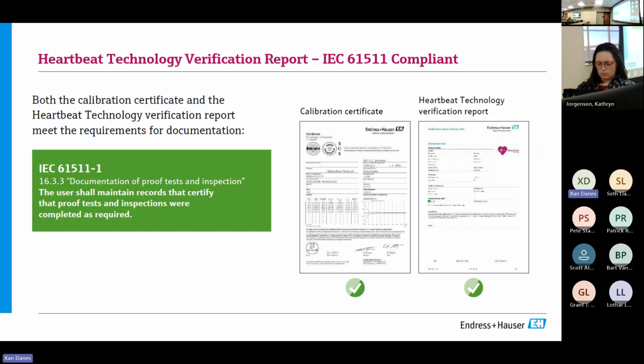So when it comes to the safety instrumented system lifecycle, the calibration certificate, and in some cases even the verification report, meet the requirements for lifecycle documentation. So being able to do a proof test or inspection, admittedly a partial proof test, the high diagnostic coverage and the redundant circuitry within a given device can often be used to extend a proof test interval, at least on the instrument itself, speaking independently of the system.